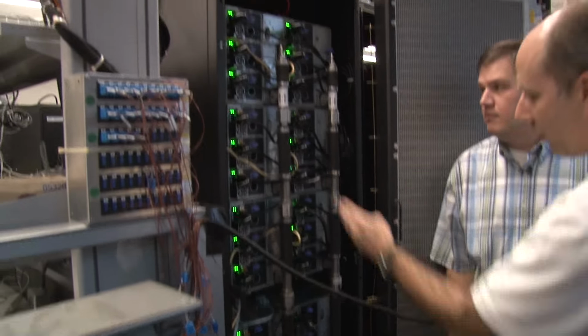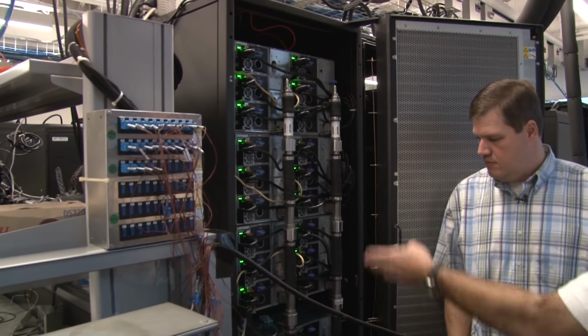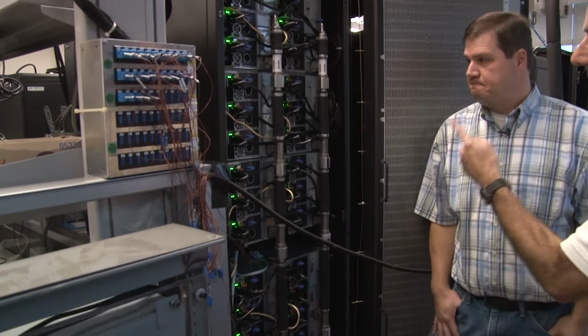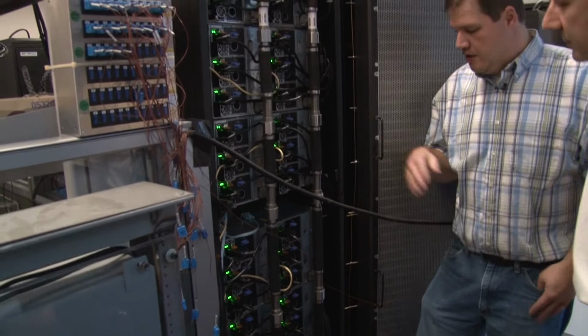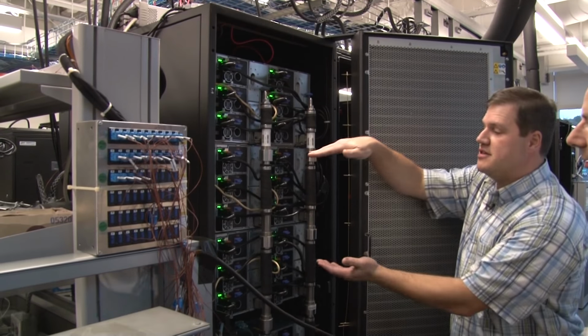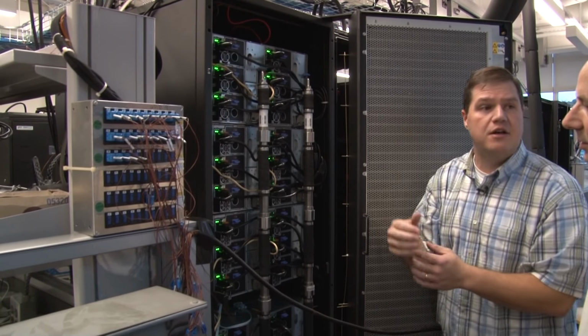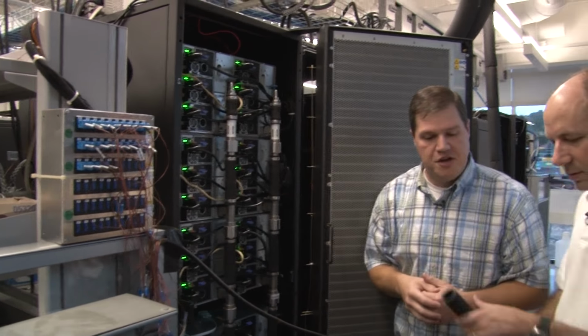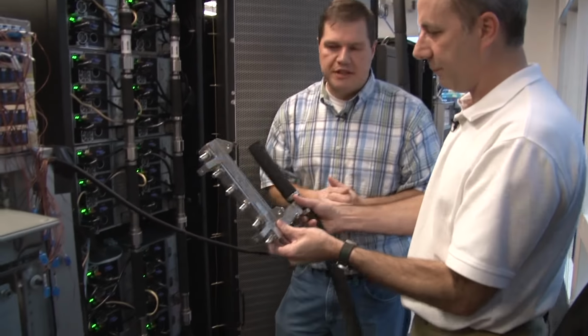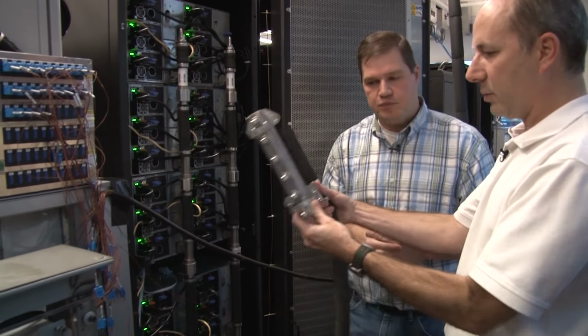You can see these black rods here, vertical rods, these are the water manifolds. Mark, what's going on here? So we have a modular-based manifold design. As you can see, the hose is coming up, and we're feeding from the bottom in this case. Each component is a manifold that goes inside the chassis to make the water connections for each node. Right, so that's what this is here, that's what the inside looks like. Okay, so walk me through what we have here. Basically you have a supply tube, and then this would scale out for however many chassis you want.